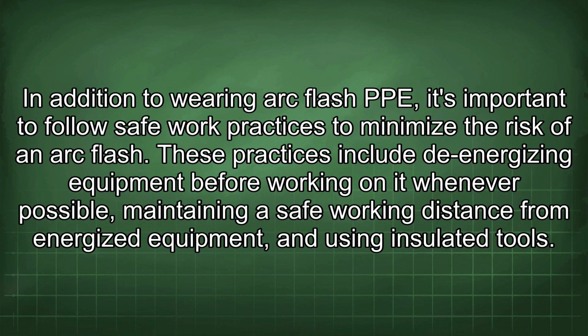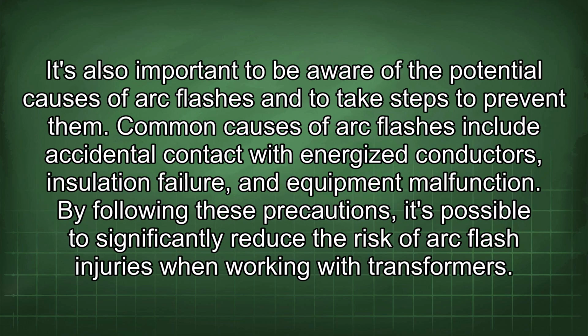insulated gloves. In addition to wearing arc flash PPE, it's important to follow safe work practices to minimize the risk of an arc flash. These practices include de-energizing equipment before working on it whenever possible, maintaining a safe working distance from energized equipment, and using insulated tools. It's also important to be aware of the potential causes of arc flashes and to take steps to prevent them. Common causes of arc flashes include accidental contact with energized conductors, insulation failure, and equipment malfunction. By following these precautions, it's possible to significantly reduce the risk of arc flash injuries when working with transformers.